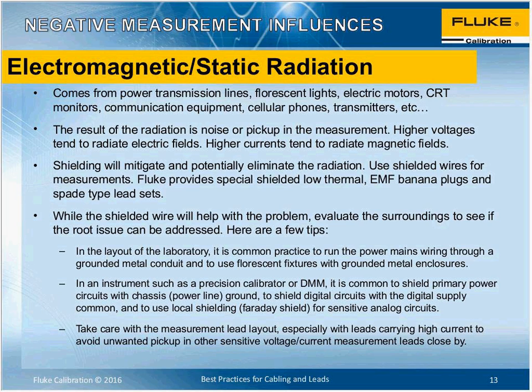So be very careful about those kinds of things, because what happens is those radiated electric fields or radiated magnetic fields can get into our measurement circuits and cause unwanted effects. And typically we're talking about higher voltages causing electric fields, and higher currents causing magnetic fields. And some of those magnetic fields actually come from the measurement circuits themselves, rather than from instrumentation, which might have transformers, line mains transformers, and so forth. So clearly some kind of shielding would be good to mitigate the effects and eliminate the radiation existing in the first place. In other words, we have the instrumentation with screens in it, and most well-designed instruments have appropriate screens inside them. It may not be the case with some of the lower cost and cheaper models.